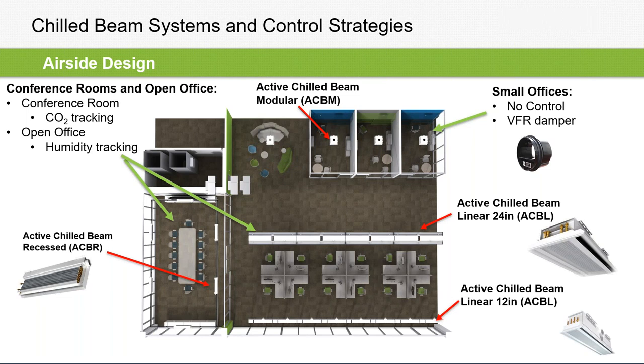I normally recommend the alarm piece, because it does take quite a while for the beam coil to sweat enough where the droplets of water on the fins are heavy enough to actually fall. And we've done many, many tests in our environmental chambers. It can take hours. So as long as you have a maintenance staff that's available to go see what the issue could be, and then address that issue, you have the choice of either turning the valve off or not. You've got a lot of options there, but really it comes down to your control sequence and how that control is set up. We can definitely talk through specific scenarios if that ever comes up, but that's definitely a great question to ask.